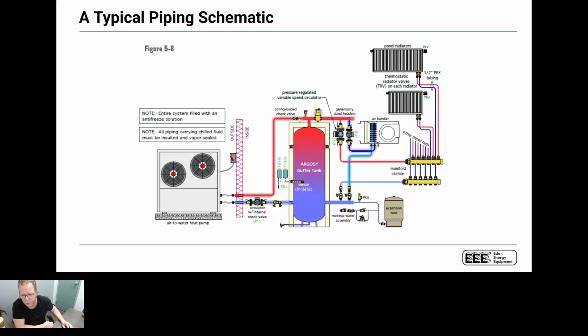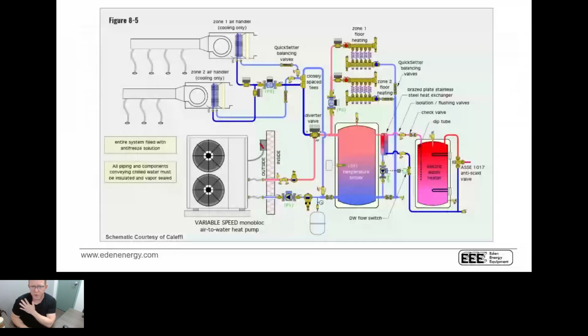So what they've done here with the piping is as they come to the top of the unit, they've sized that piping so the flow velocity drops below 2 feet per second. And what it means is that in a heating situation, we're getting all of the energy going out to the emitters, which is really, really cool, right? So if we don't have any emitters running, it's charging the buffer tank. If the emitters are running, whatever the water temperature we need is going directly to the load. So it's a very, very cool, well, hot way, I guess would be the way to put it, that you could design the system and make the system work.